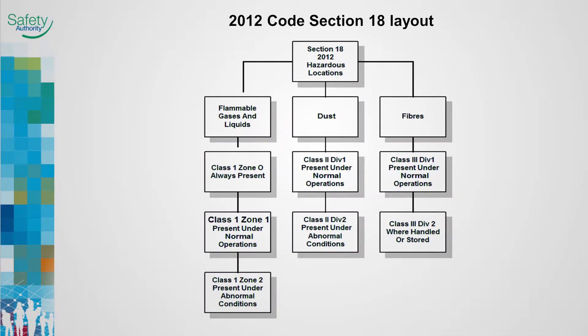In the 2012 Code, hazardous locations were organized into three classifications depending on the nature of the hazard: flammable gases or vapors, combustible or conductive combustible dusts, and easily ignitable fibers or flyings. In the 2015 Code, hazardous locations have been reorganized into two classifications: Explosive Gas Atmospheres, which includes gases, vapors, or mists.